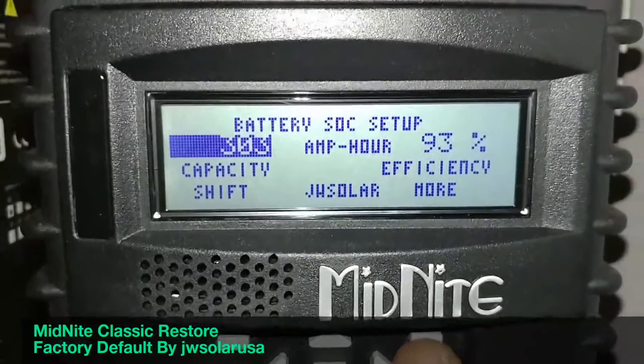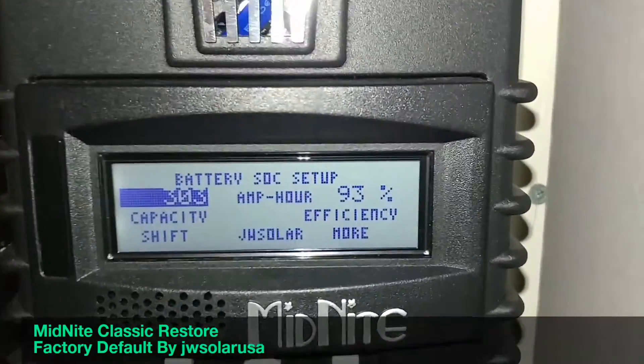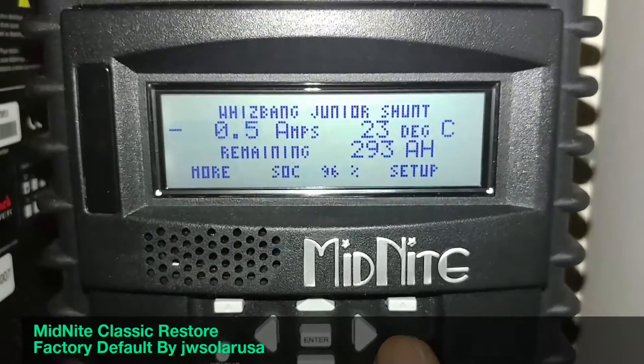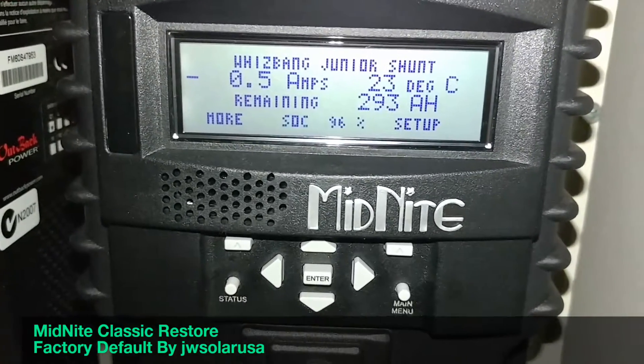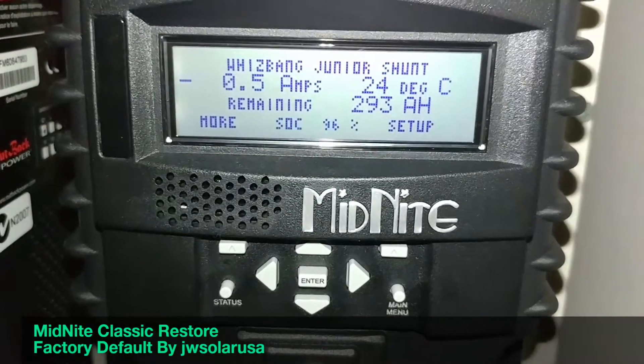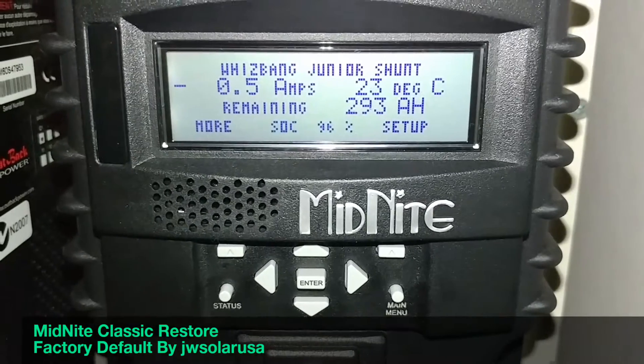Efficiency is one of the most critical settings when you go to factory default, because everything goes back to the factory default. The factory default that MidNite Solar sets is 94%, so you need to adjust this depending on what kind of batteries you have.